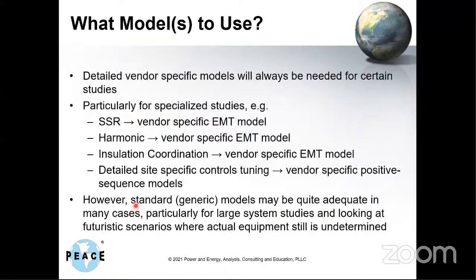But let's say you're looking at a particular site close to a series cap and you're worried about SSR. Then you need the vendor-specific EMT model, and you need communication between the vendor, the plant owner, and the transmission planner to study that scenario and make sure you can mitigate that problem. Or if you're worried about harmonics, insulation coordination, or even detailed site-specific controls tuning, those all require vendor-specific models. So it's really important to understand what we're trying to study, and then we can choose the right model for the task.